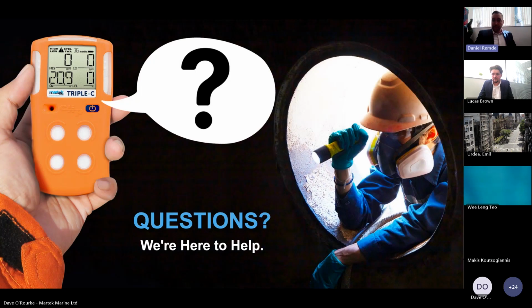Marcus, no calibration on the Triple C. What is the drift of the sensor over time? Marcus, it's got an infrared LEL sensor, so it's not prone to drift, and any minute drift would be able to be zeroed without the need for calibration. And it's very simple to bump test. You don't need any extra equipment, so there's no bump station. You can get a bump station, but it's not required. All you need is a canister of gas and a fixed flow regulator. Each unit comes with a clip that forces the gas over the sensors and goes on the front of the gas detector. And we do recommend bump testing regularly, preferably before use, as with every gas detector.